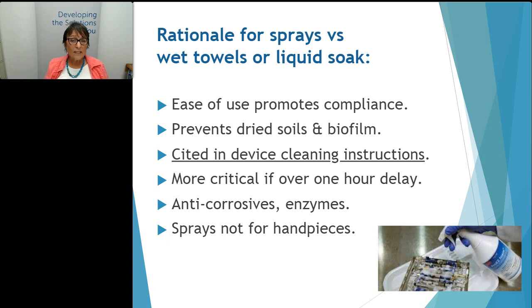And it's especially important that you have a strategy, whatever it is, if you have frequent delays. And this oftentimes happens in busy dental offices where there may be 3, 4, 5 dentists, but there's not an instrument processing technician. So even though in dentistry we might be very quick, and it's only 10 feet from the patient treatment area to the instrument processing area, that doesn't help if an instrument sits there in the instrument processing for 30 minutes, an hour, 2 hours. So this is an important and very helpful procedure for dentistry to avoid dried soils from point of use to instrument processing.